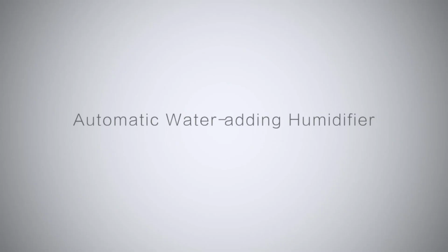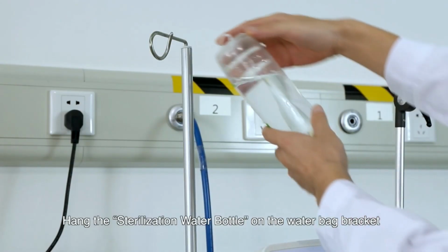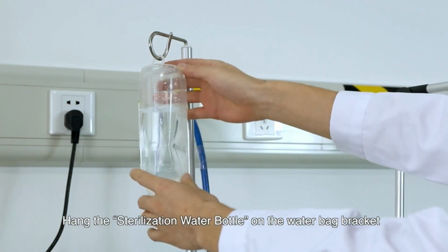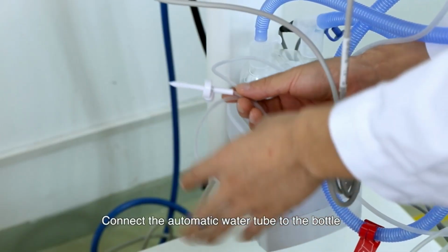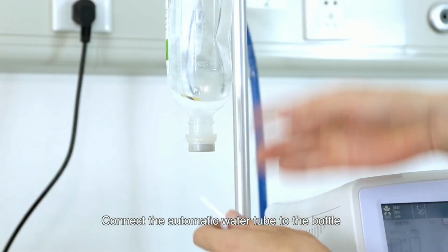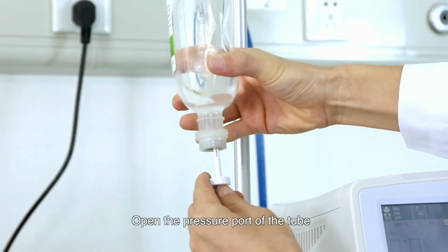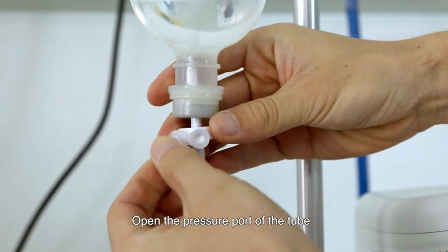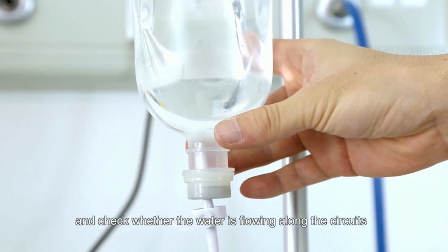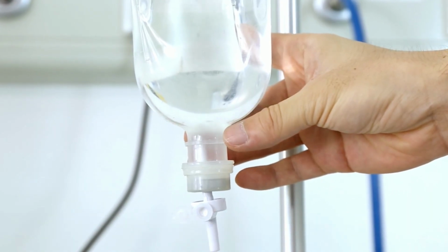There are two kinds of humidification pots. One is able to add water automatically and the other manually. For the automatic water adding humidifier, hang the sterilization water bottle on the water bag bracket. Connect the automatic water tube to the bottle. Open the pressure port of the tube and check whether the water is flowing along the circuits.